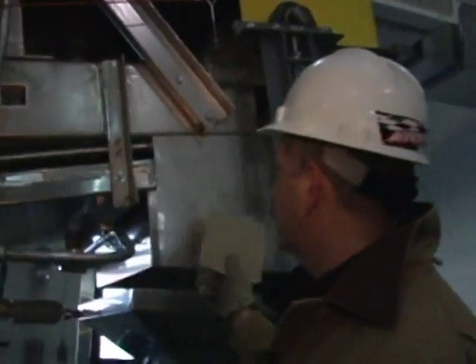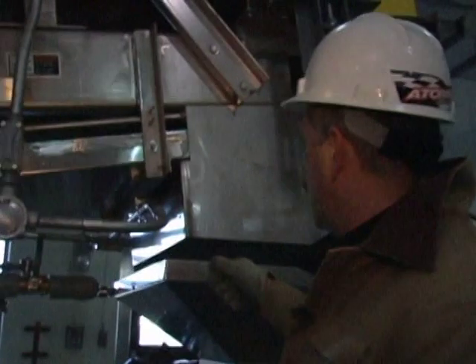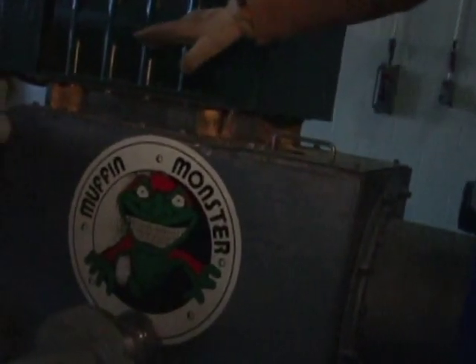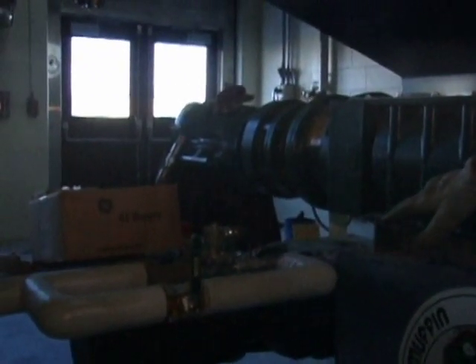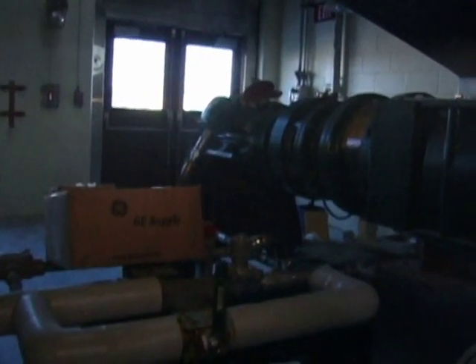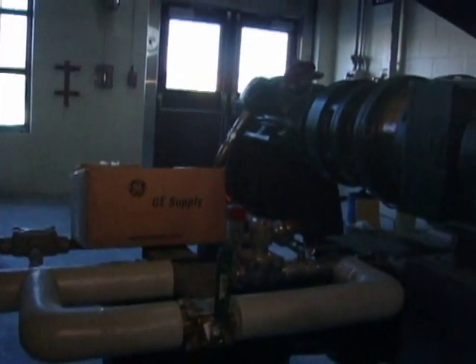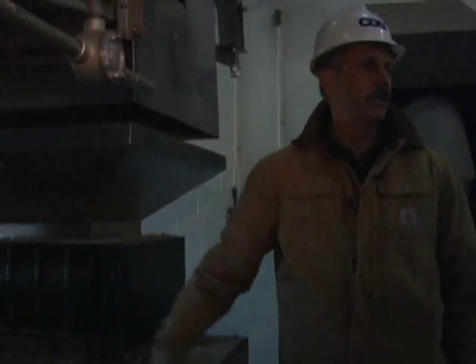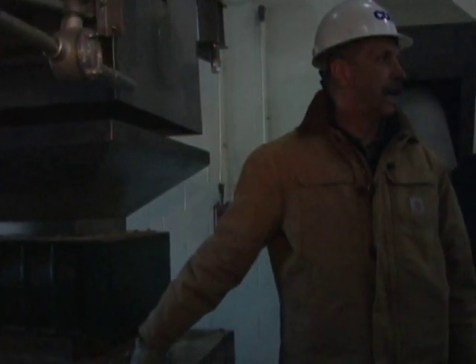From here, the screenings are discharged into the wash press, which is basically a grinder operation, followed by a washing mechanism where the organics are intended to be washed out of the material. There's an auger system within the lower chamber. There's a spray water line that comes on both for the grinder as well as the washing chamber itself, so that as the auger runs in the forward and reverse direction, and that's been set up on a time sequence, namely I believe it's 30 seconds in the forward direction with an 8-second stop and then 25 seconds in the reverse direction. What that's doing is actually applying water to the screenings as it's being discharged and washing the material to try to wash the organic material out of the screenings.